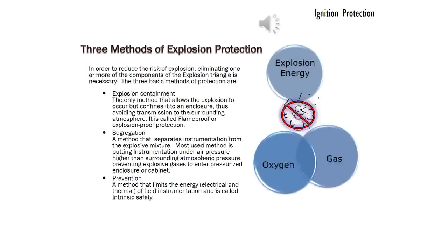Segregation, a method that separates instrumentation from the explosive mixture. Most used method is putting instrumentation under air pressure higher than surrounding atmospheric pressure, preventing explosive gases to enter pressurized enclosure or cabinet. Prevention, a method that limits the energy, electrical and thermal of field instrumentation and is called intrinsic safety.